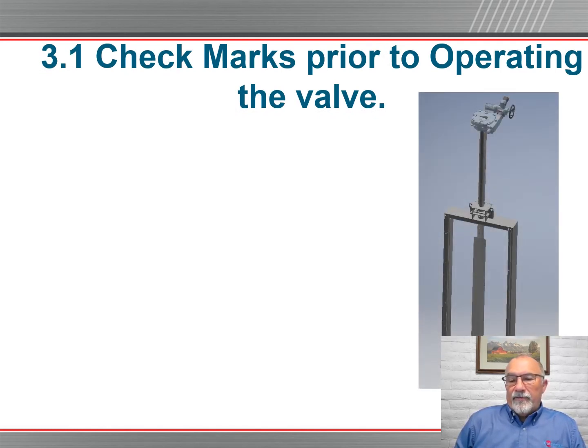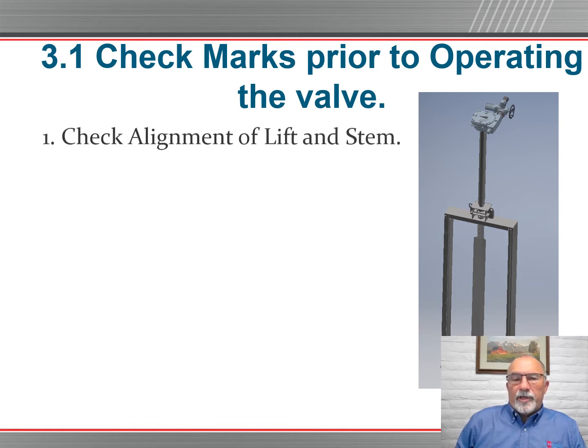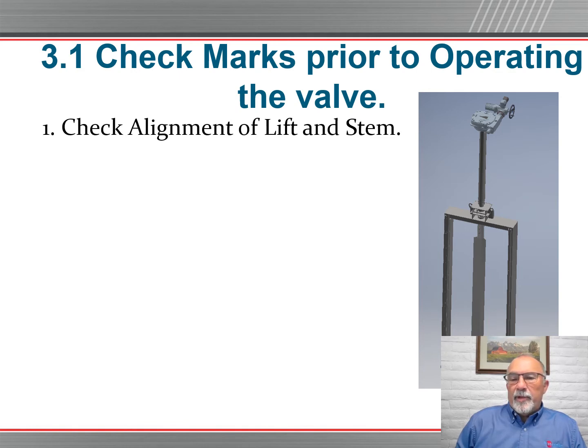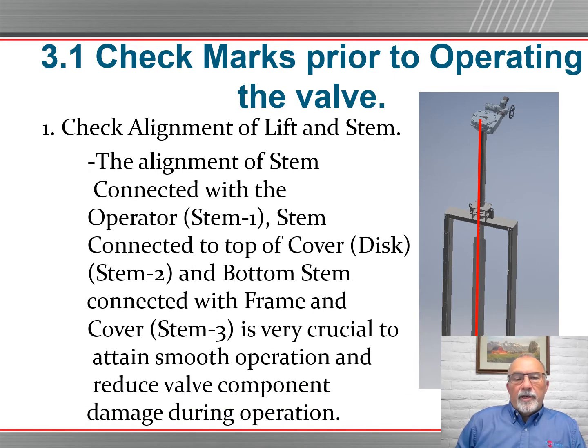Check marks prior to operating the valve, continued. Notice the valve on the right. Again, very similar to what you guys have there on this Manitoba project. Check the alignment of the lift and stem. Make sure everything is truly in alignment. Notice the red line. You should be able to draw directly from the center of the geared operator right down through the center of your pivot shaft number 3. The alignment of the stem connected with the operator, stem 1, stem connected at the top of the disc, stem 2, and the bottom stem connected with the frame, stem 3, is very crucial to attain smooth operation and reduce valve component damage during operation.